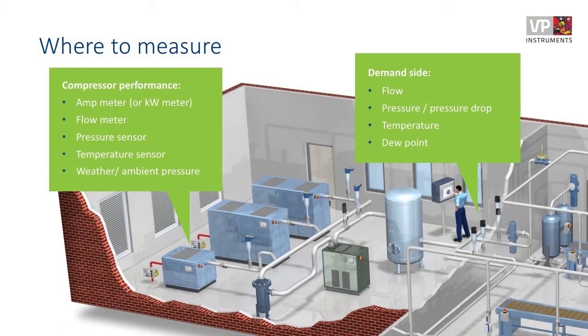If you want to monitor compressor performance, you could install amp meters or kW meters for each compressor. Then you could also add a flow meter at the discharge pipe, especially if you have a large turbo compressor, a centrifugal compressor. That can be interesting because then you can see the ratio between output and input. If something happens to the compressor, like a polluted inlet filter, output flow changes and the ratio between output flow and consumed power will change. And that might be a trigger to clean the filter.